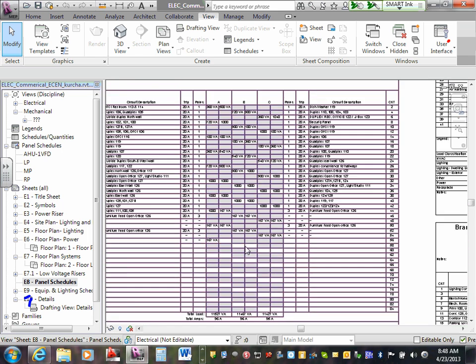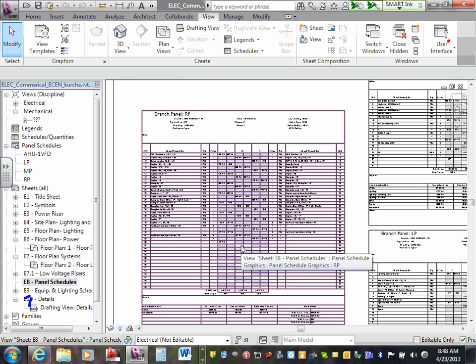53, 54. I have 54 circuits. So we need to build a system for 54 circuits. We're going to use multi-wire branch circuits, guys. Do me a favor, do you have a calculator handy? Take 54 divided by 6. We're going to use the same conduit system. 54 divided by 6 is 9. Now I have to carry 9 conduits all the way up.